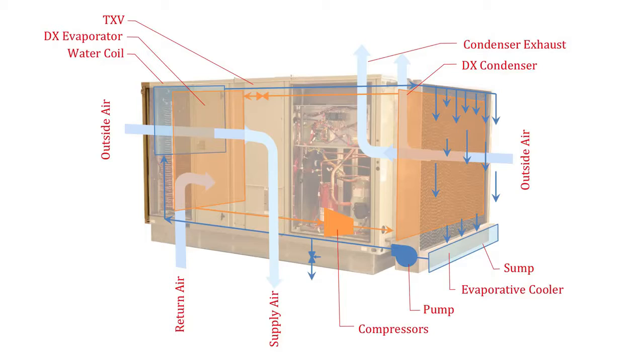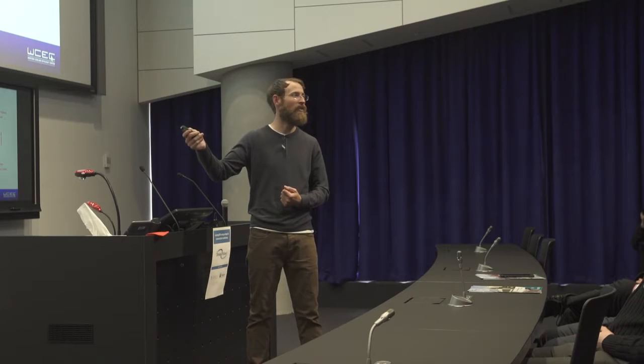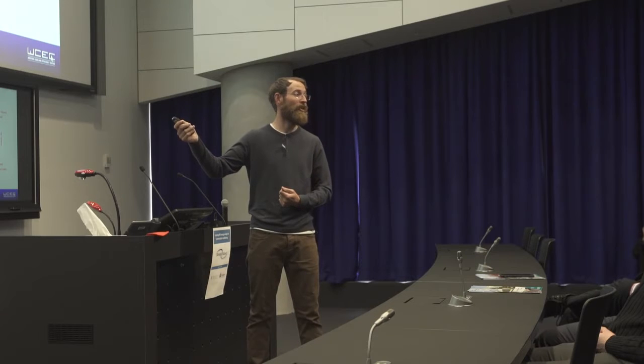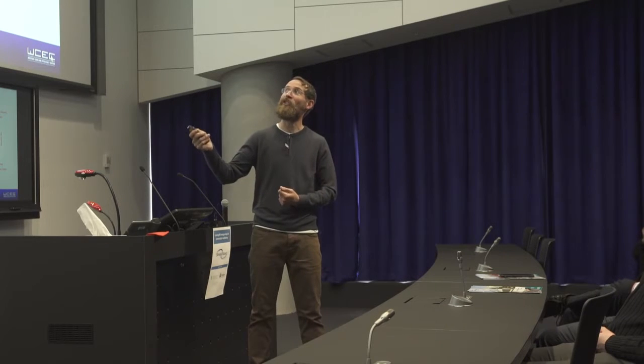This improves the efficiency of the vapor compression circuit considerably. But then at the same time, that water is cooled down to very near the wet bulb temperature. And they use that wet bulb temperature water circulated back through to the other side of the system in a water-to-air heat exchanger to pre-cool all of the ventilation air that's entering the system, which reduces the load for the vapor compression circuit. So they call it the dual cool. They're doing two things with it, improving the efficiency of the circuit and reducing the total load of vapor compression.